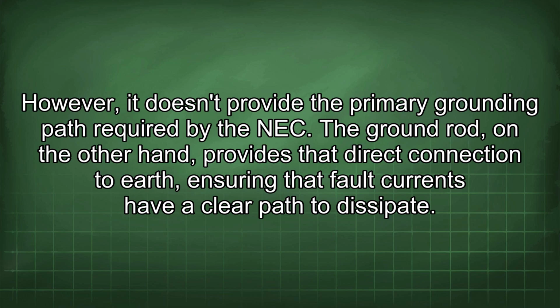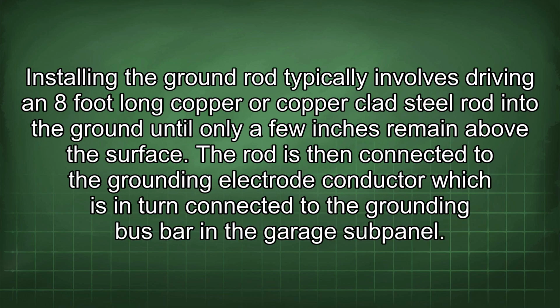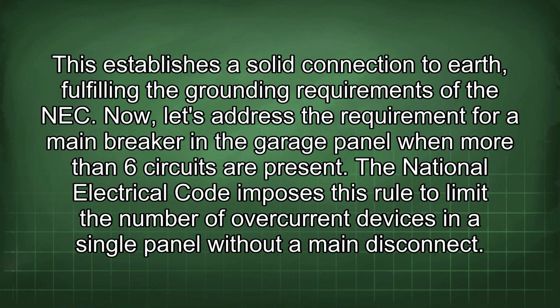The ground rod, on the other hand, provides that direct connection to earth, ensuring that fault currents have a clear path to dissipate. Installing the ground rod typically involves driving an 8-foot-long copper or copper-clad steel rod into the ground until only a few inches remain above the surface. The rod is then connected to the grounding electrode conductor, which is in turn connected to the grounding bus bar in the garage subpanel. This establishes a solid connection to earth, fulfilling the grounding requirements of the NEC.